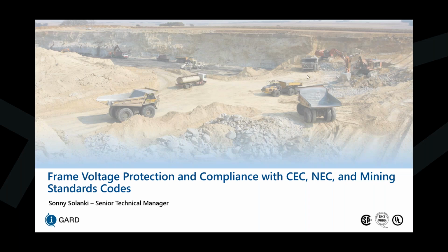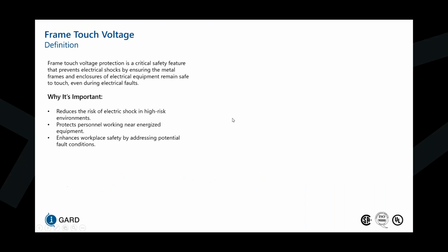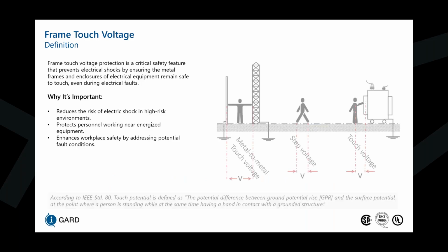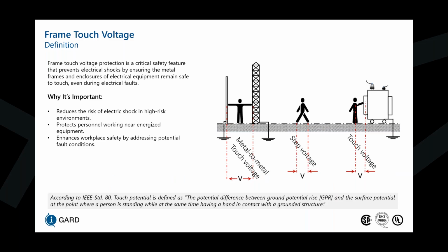Thank you, Devansh. Today's presentation is on frame voltage protection and compliance with CEC, NEC, and mining standards codes. So to start off with, frame touch voltage. Frame touch voltage protection is a critical safety feature that prevents electrical shocks by ensuring that metal frames and enclosures of electrical equipment remain safe to touch even during electrical faults. So it's important to do this to reduce the risk of electric shock in high-risk environments, protect personnel working near energized equipment, and enhance workplace safety by addressing potential fault conditions.